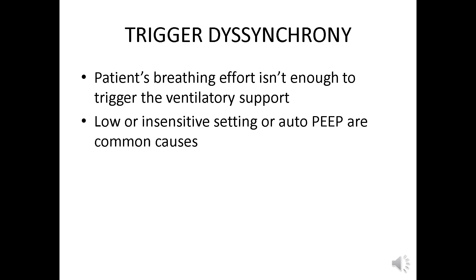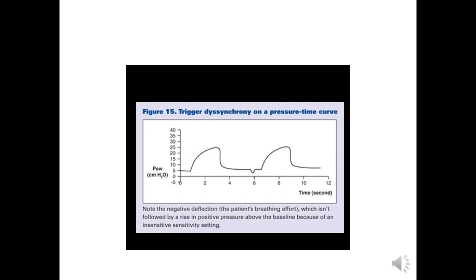Next is trigger dyssynchrony — the patient's breathing effort is not enough to trigger ventilatory support. This can be due to auto-PEEP or insensitive trigger settings. On the pressure-time curve, the negative deflection representing the patient's breathing effort is not followed by a rise in positive pressure. All breaths are ventilator-initiated even though the patient is making adequate negative pressure effort.